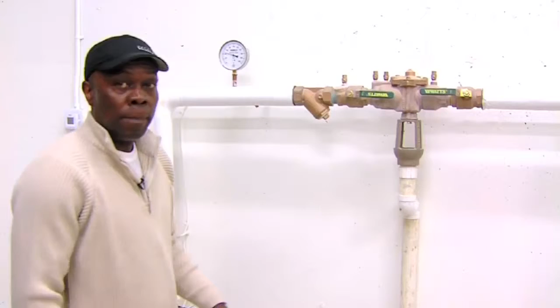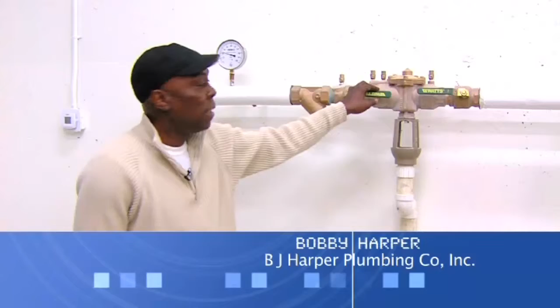Here we have a backflow preventer, which basically prevents the water from coming back into the system. This is a Watts, the 1315, which comes with a check valve and a flapper. Every so often you do have to service the flapper, it will get stuck, so you take it out to clean it. The strainer here also has to be cleaned every so often. They need to be tested maybe once every 2 years to make sure they're still working properly. These are your test ports, and this is your drain, a blow down off the backflow preventer. Basically, that's it with the backflow preventer.